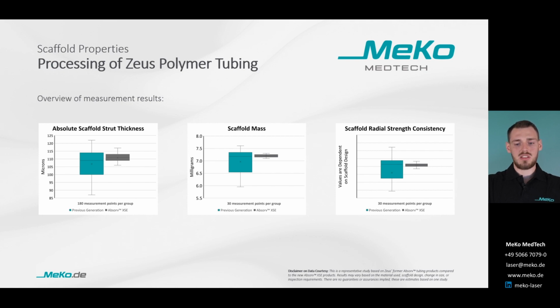The scaffolds then have been tested in the MeKo MedLab for strut thickness, which is shown on the left, scaffold mass in the middle, and radial strength consistency on the right. The strut thickness is directly linked to the wall thickness of the tubing, while the scaffold mass is a combination of wall thickness and strut width consistency. The latter is determined by the laser cutting. Each of the test results shows significant improvements and demonstrates the benefit for the device.